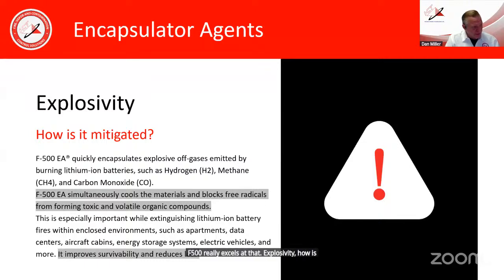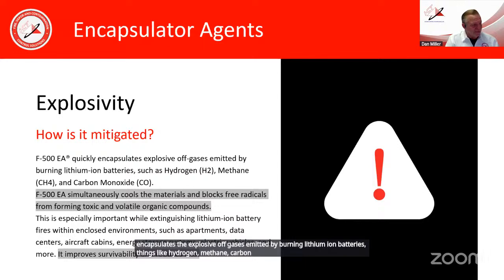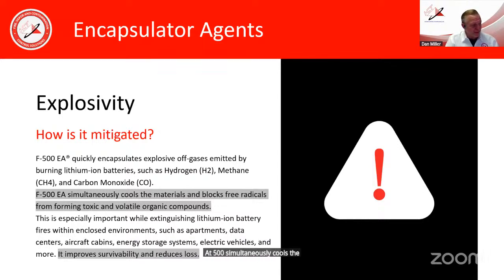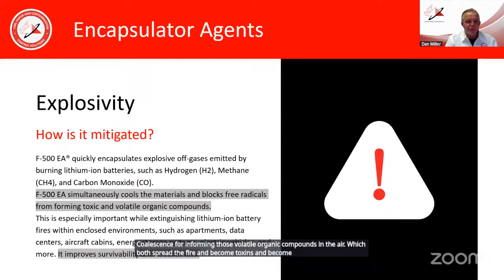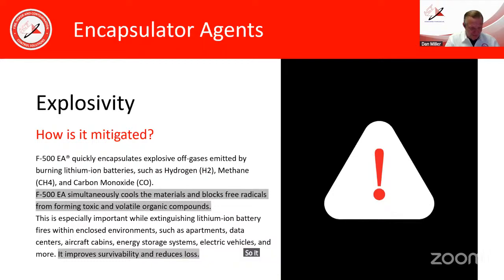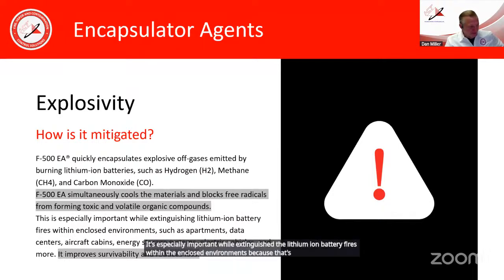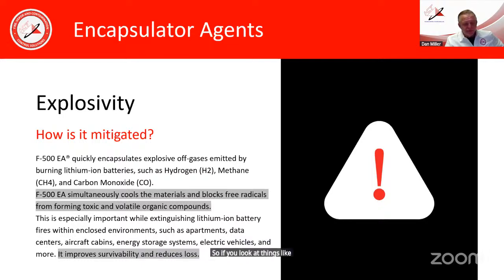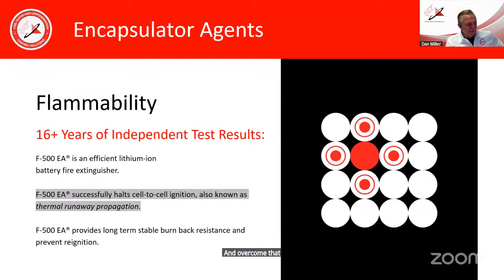Explosivity, how is it mitigated? F500 quickly encapsulates the explosive off-gases emitted by burning lithium-ion batteries, things like hydrogen, methane, and carbon monoxide. F500 simultaneously cools the materials and blocks free radical coalescence from forming volatile organic compounds in the air, which both spread the fire and become toxic or explosive if it's a vapor-only thermal runaway. So it really handles the bulk of lithium-ion battery hazards through simple application. This is especially important when extinguishing lithium-ion battery fires within enclosed environments, because that's where they become explosive. So in places like parking garages, data centers, aircraft cabins, and energy storage systems, it really helps improve survivability, reduce loss, and overcome that explosivity and toxic vapor production.